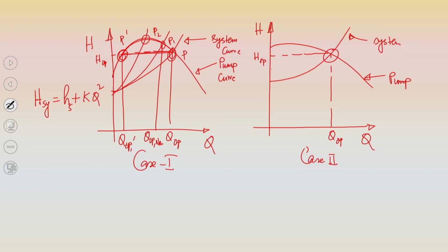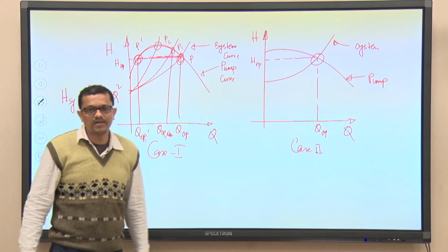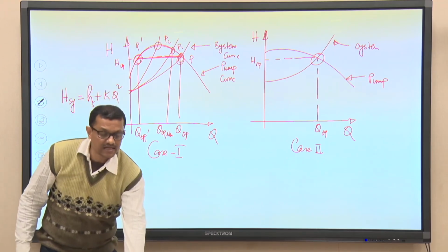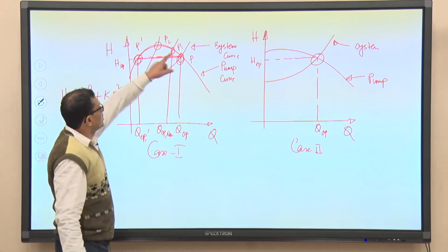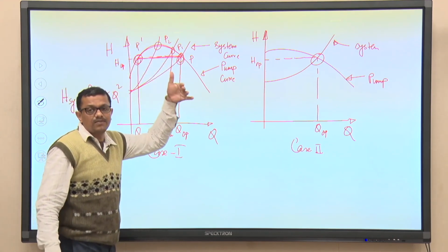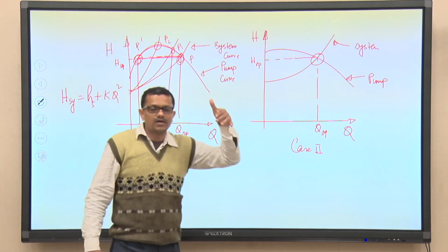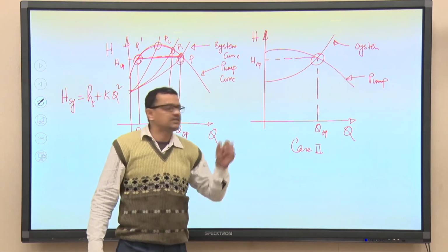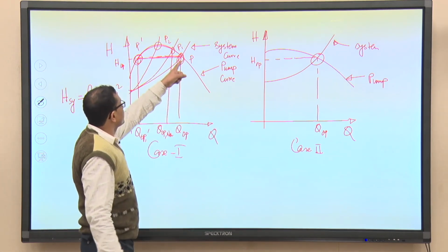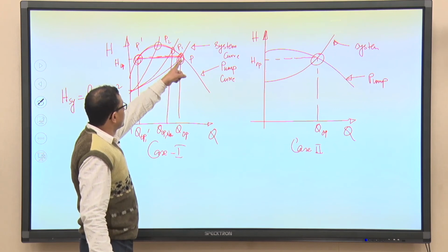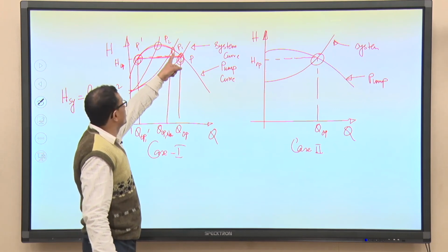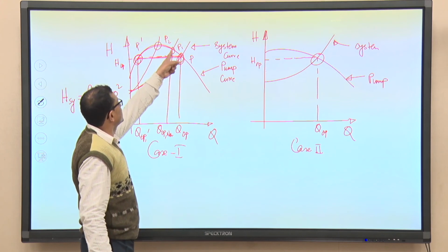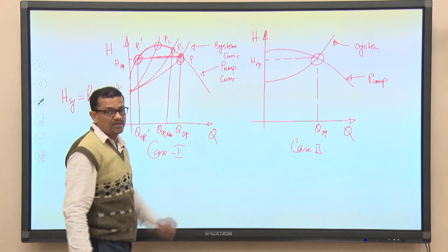So, this is very detrimental from the pump operation of a radial flow pump. The idea is, if because of malfunctioning of the valve, say the operator closes the valve from the original to a new position, the system resistance curve shifts and the new operating point is P1.